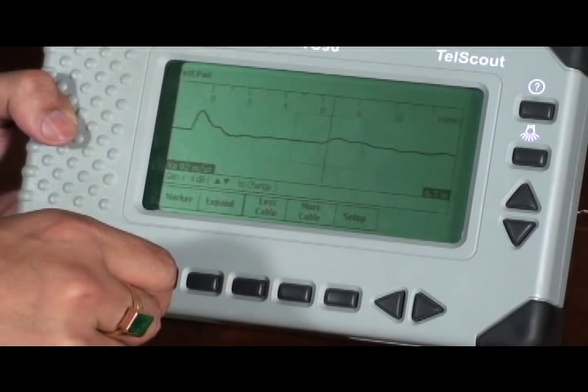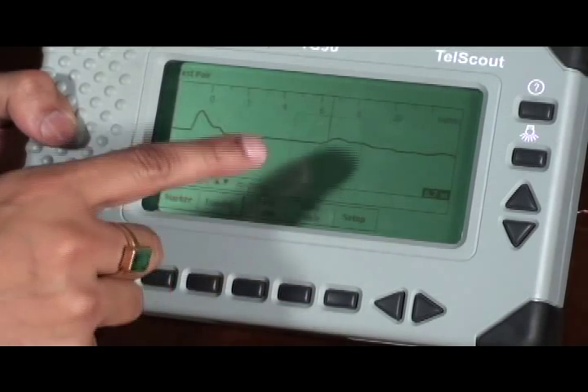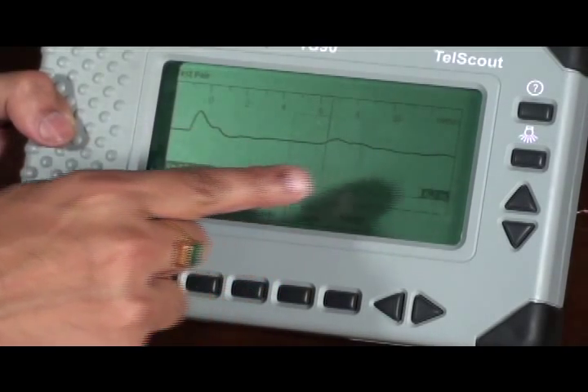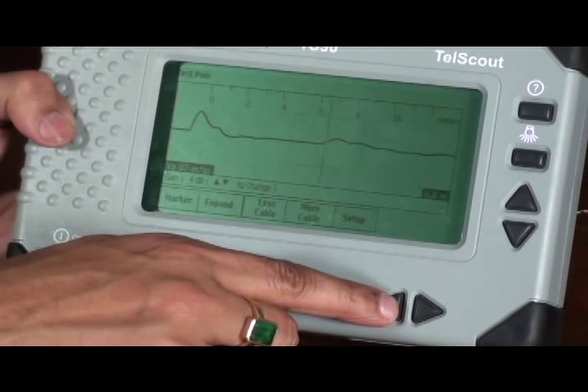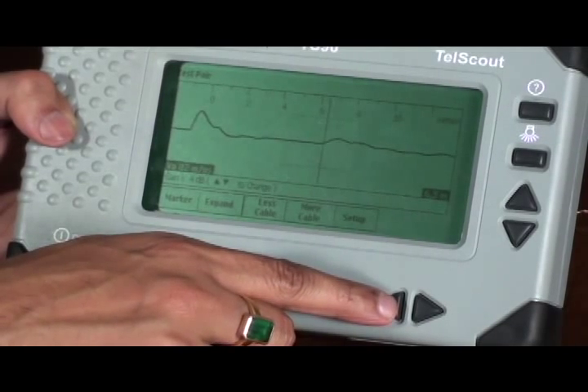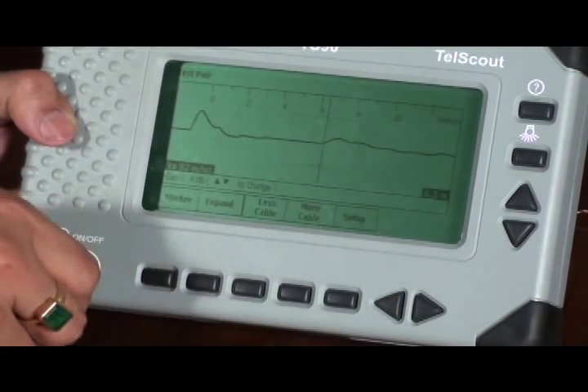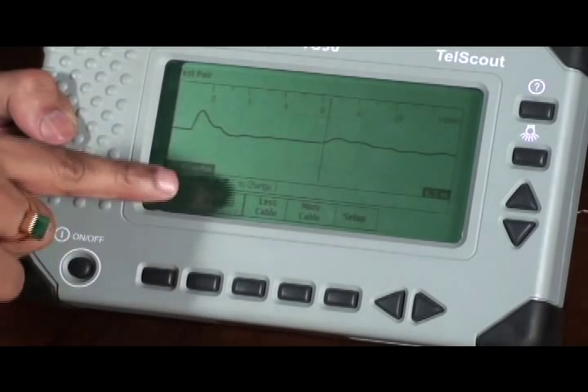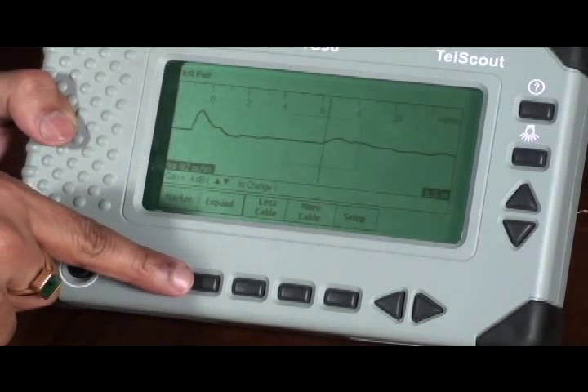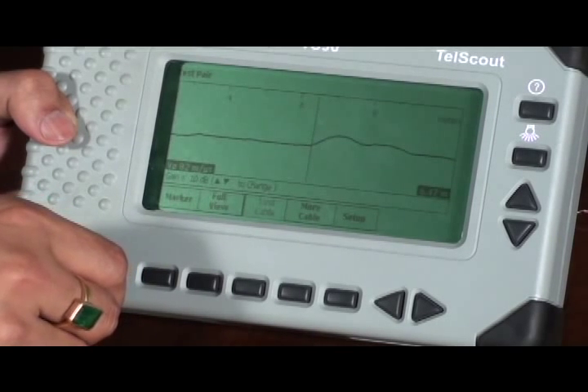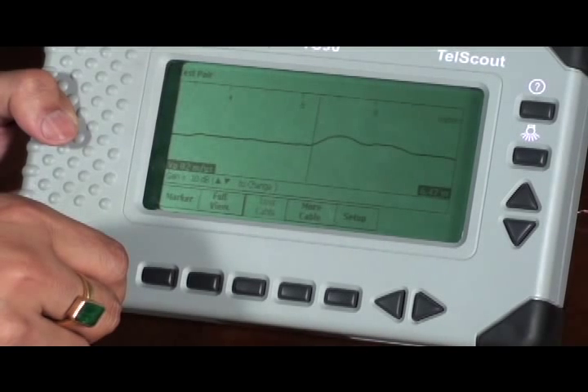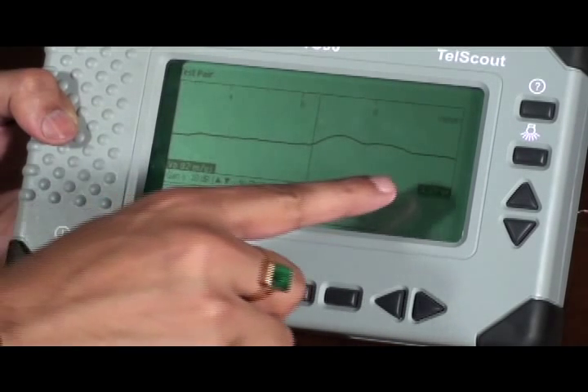The graphical representation shall again appear. We now bring the cursor at the beginning of the upward spurt again. Press the button expand for a better and enlarged view. We now see that the cable length is shown on the screen as 6.47 meters.